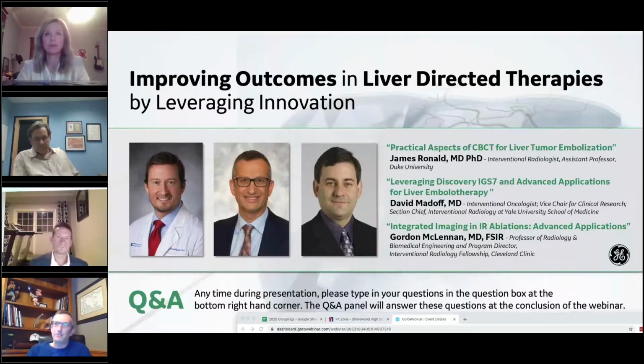Because basically, when you use other vendors, in order to reduce the streak artifact, at least for liver cases, we always have to put the arms up. And it makes the procedure much more complicated, much more difficult for the techs and nurses. And it often allows one to decide, or be talked out of, actually doing that cone beam CT. So with this software, with this algorithm that subtracts out the bones and the ability to leave the patient's arms at their side rather than over their head, it just makes the whole workflow so much better. So I just wanted to make sure that was not overlooked, because when I tell people about this, they get very, very interested. Yeah, understandably so. Thank you.